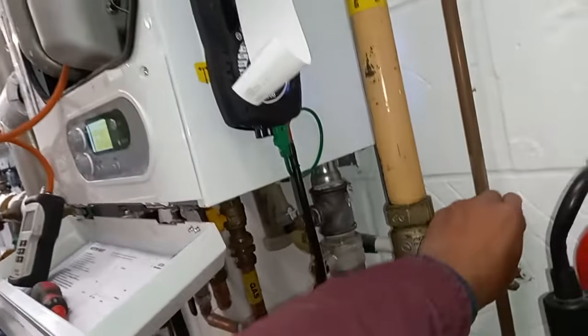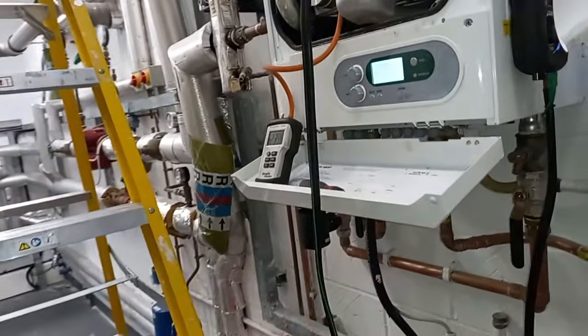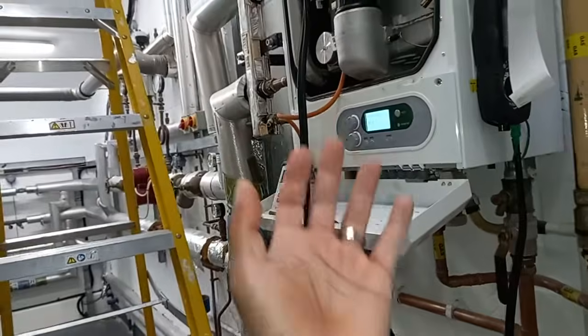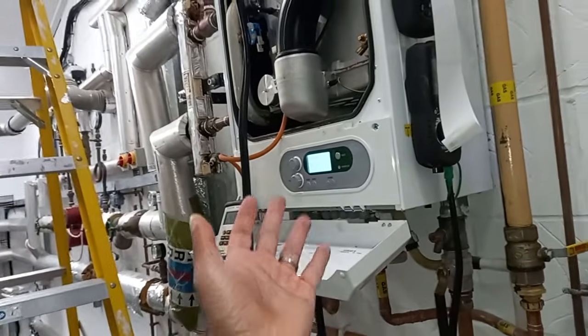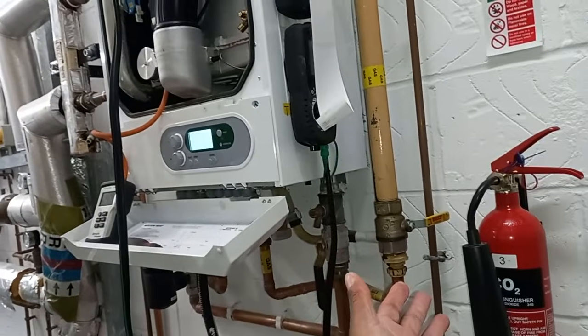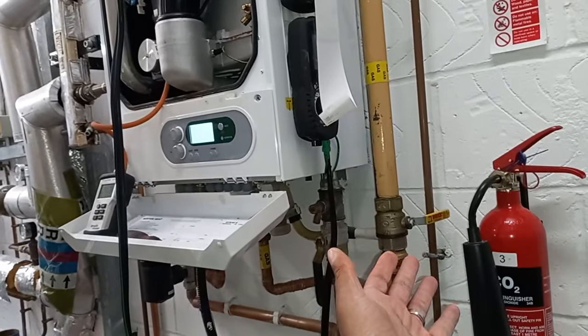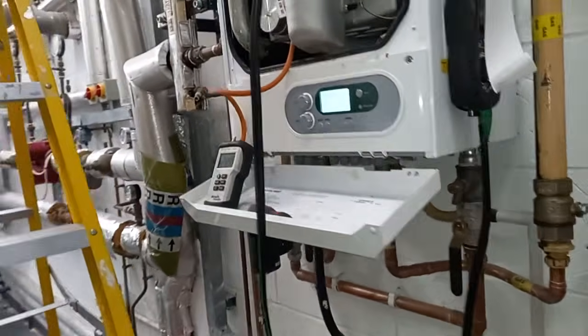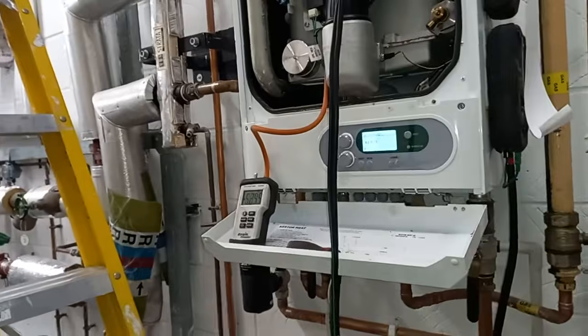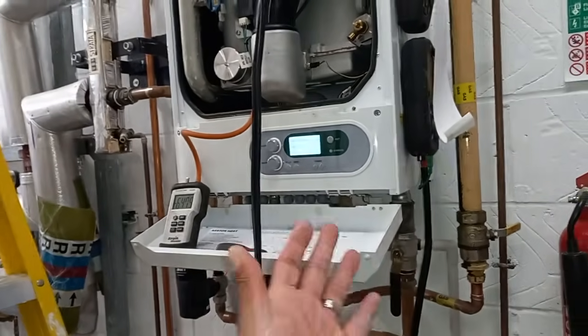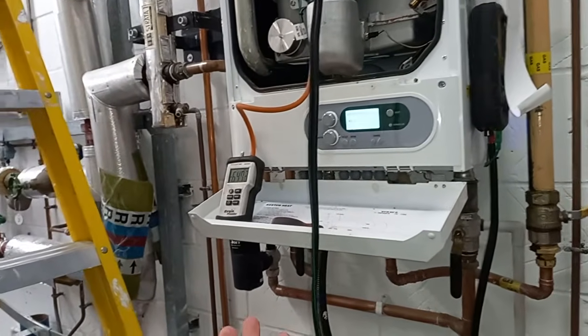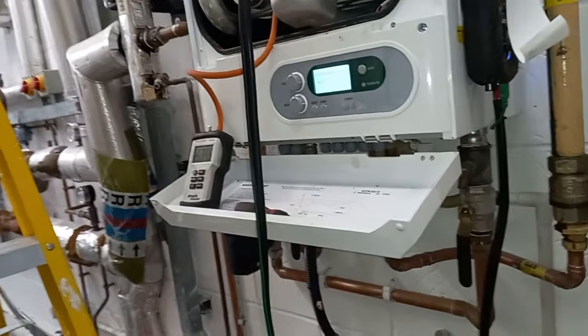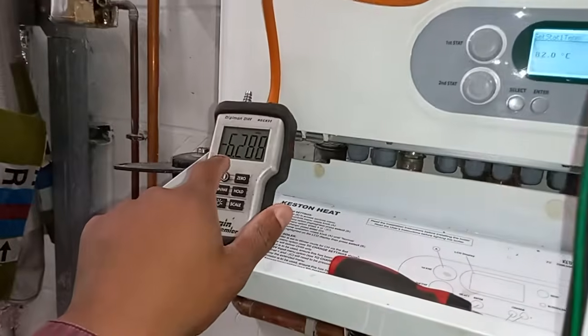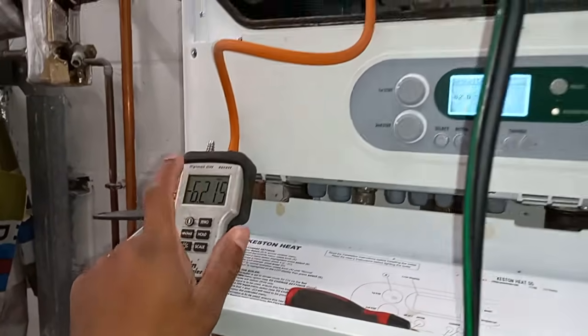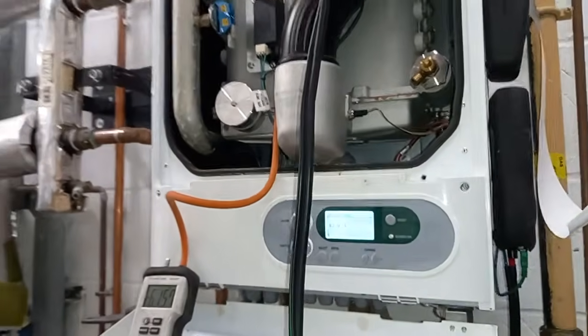Going to do my safety shut off. My safety shut off time, so I can do my countdown of my 1, my 2, my 3, my 4, and I can time how long it takes for the boiler to shut down, the safety shutdown time when the gas supply is interrupted. That's another check you can do. So it's not lighting because the gas supply has been shut. So how long is it going to take? You can clearly see the gas valve open there because the pressure dropped. That's a good test for checking that your gas valve is working.